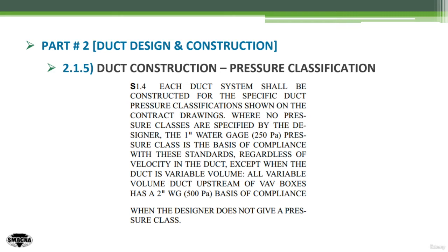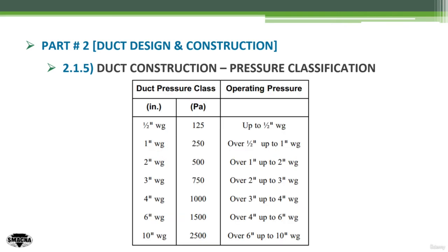The exception is variable volume systems: all variable volume duct upstream of the VAV boxes should have a two-inch water gauge basis of compliance when the designer does not give a pressure classification.